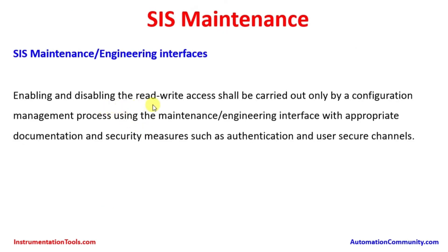Enabling and disabling read/write access shall be carried out only by a configuration management process using the maintenance engineering interface, with appropriate documentation and security measures such as authentication and user secure channels. For example, there could be bypass requirements — such as a pump run enable — where the pump may not be running due to plant non-requirement. In such cases, all actions shall be captured in documentation so that any mistakes or failures can be corrected.